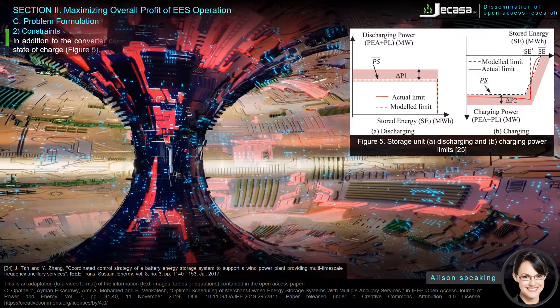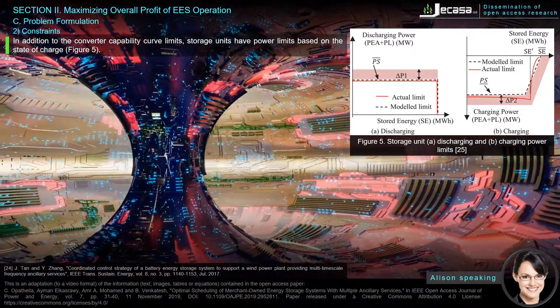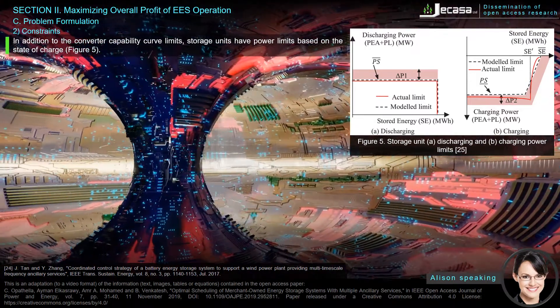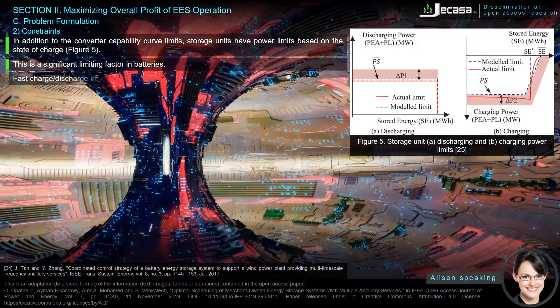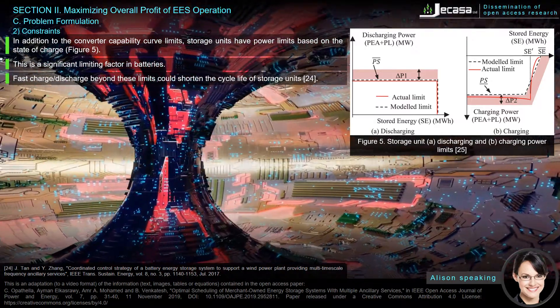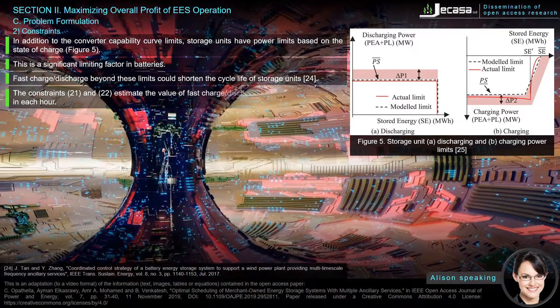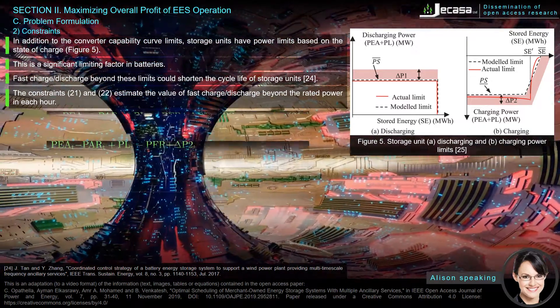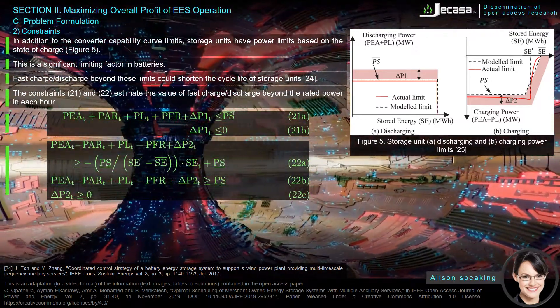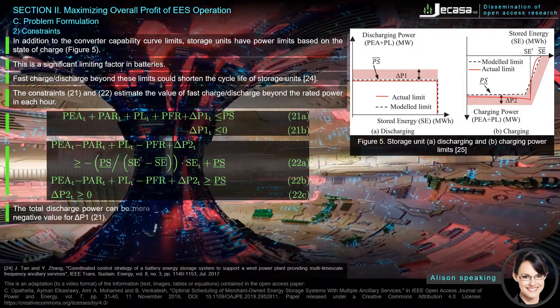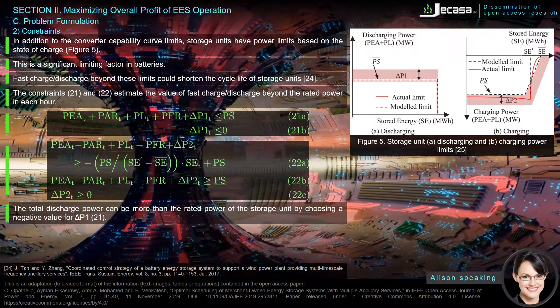In addition to the converter capability curve limits, storage units have power limits based on the state of charge, as shown in Figure 5. This is a significant limiting factor in batteries — fast charge/discharge beyond these limits could shorten the cycle life of storage units. Constraints 21 and 22 estimate the value of fast charge/discharge beyond the rated power in each hour. The total discharge power can be more than the rated power of the storage unit by choosing a negative value for delta P.